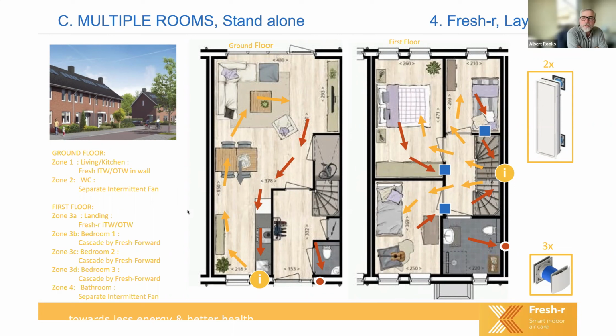But if somebody goes in there and closes the door and CO2 starts popping up at 700, 800, 900, 1,000, then essentially it sees that activity and turns on the fan. And as it turns on the fan, it pulls air out of the room. And as it pulls air out of the room, we've got an undercut under the door, and it pulls fresh air into the room because we're supplying right at the head of those stairs.